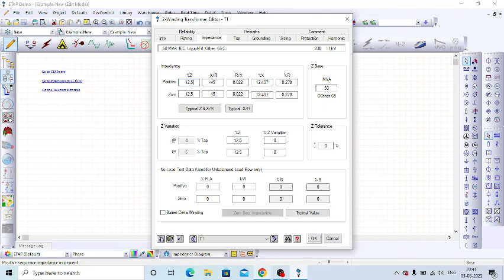So those transformers mostly comply with IEC or ANSI standards. In IEC, there is a requirement for tolerance. So all transformers complying with that standard have to keep the impedance tolerance within that limit. So that tolerance we will consider. The positive tolerance we have to consider for the load flow study, and the negative tolerance we have to consider for the short circuit study.